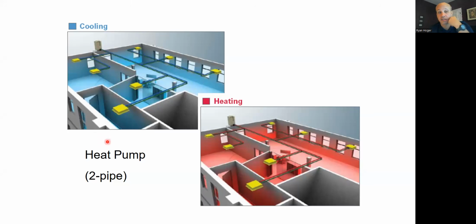They can either be in cooling mode in blue, or they can be in heating mode in red. I cannot have one in cooling while one is in heating. I can turn some of them off. Like I can say, you know what? This whole perimeter right here needs heat. All 3 of these guys need heat. But these zones don't need any heat right now. They're on the west side. The sun's hitting them. I could turn these 4 off while running those 2 for heat. But I can't give these 4 cooling while giving those 3 heat. Right? They'll have to wait their turn because the outdoor unit can only do 1 mode at a time.